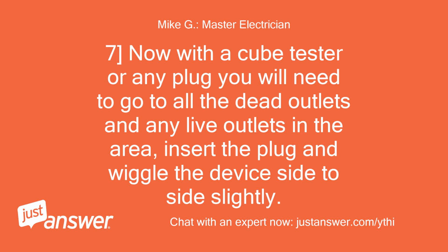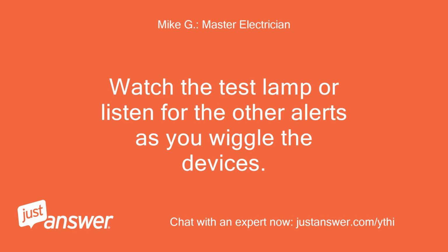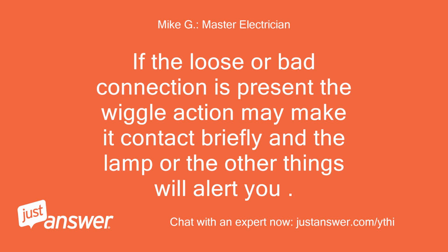7. Now with a cube tester or any plug you will need to go to all the dead outlets and any live outlets in the area, insert the plug and wiggle the device side to side slightly. Watch the test lamp or listen for the other alerts as you wiggle the devices. If the loose or bad connection is present, the wiggle action may make it contact briefly and the lamp or the other things will alert you.